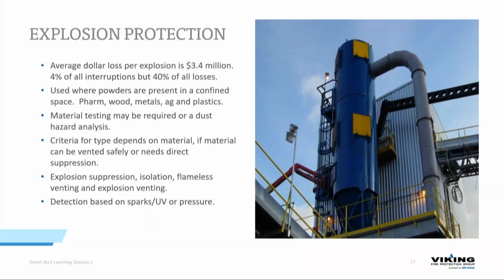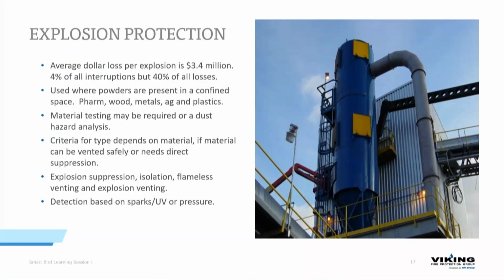Explosion protection. Average dollar loss per incident is $3.4 million. They only account for about 4% of actual fire losses in facilities, but 40% of all losses, 4% of interruptions. Used where powders are present in a confined space. Pharmaceuticals, woods, metals, ags, plastics, anything that has flammable dust. Material testing may be required or a dust analysis. Criteria for the type of explosion protection depends on material. If the material can be vented safely or if it needs direct suppression.